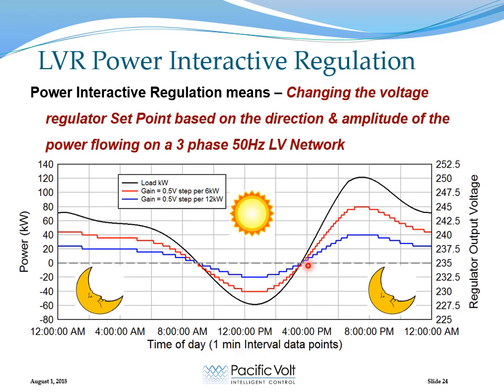Then towards sundown, it again transitions through the 0 point, which we call the null point, and this null point can be adjusted. It could be 240, 235. You have control over that. And as the load climbs, we raise the voltage in proportion, and that offsets the voltage drop from higher than normal power flow. So we can maintain voltage compliance on the LV networks up to the thermal limit of the feeder as it's designed.